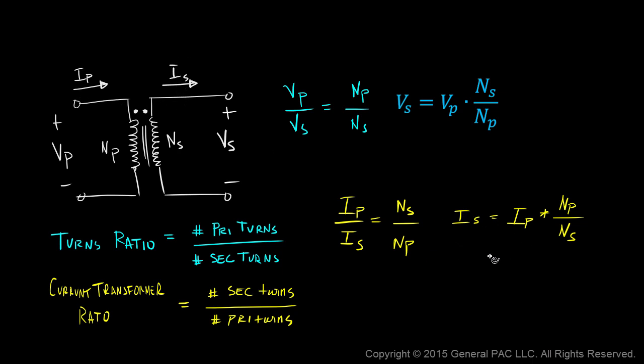If we were to design a current transformer, we would want a small secondary current — that's the whole purpose of a current transformer. To have a small secondary current means we either need very few primary turns or a very large number of secondary turns.